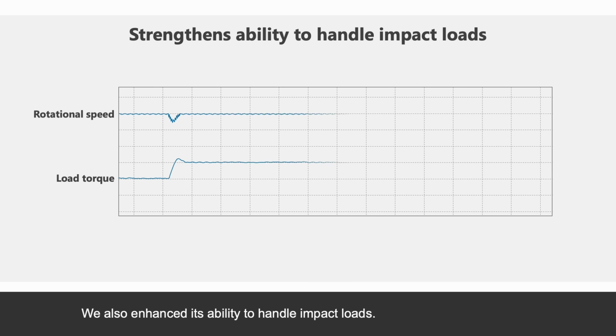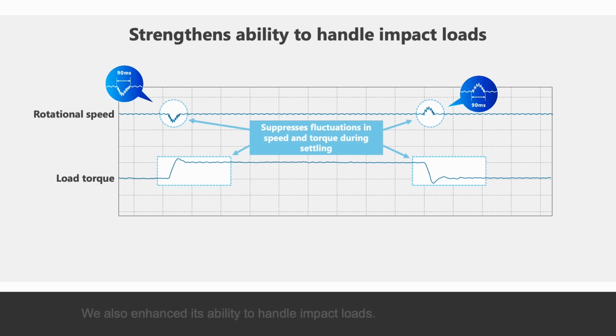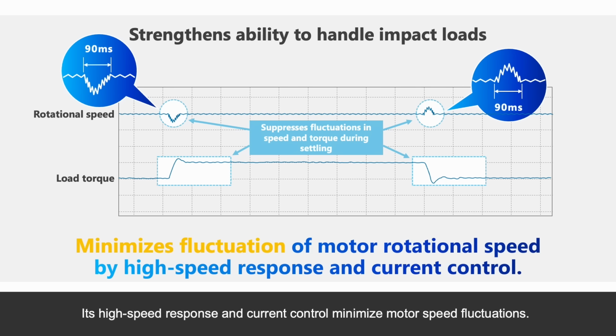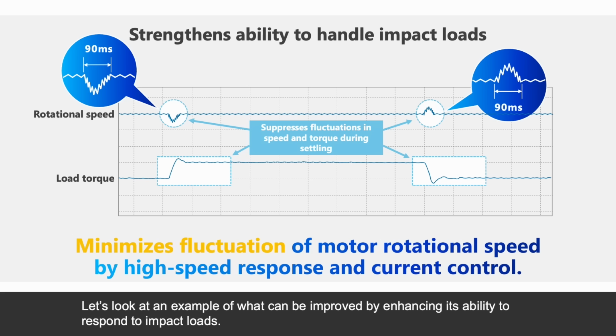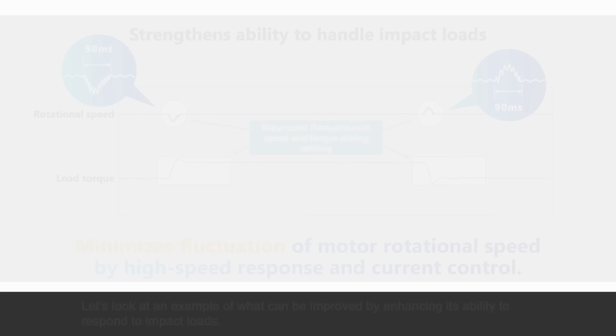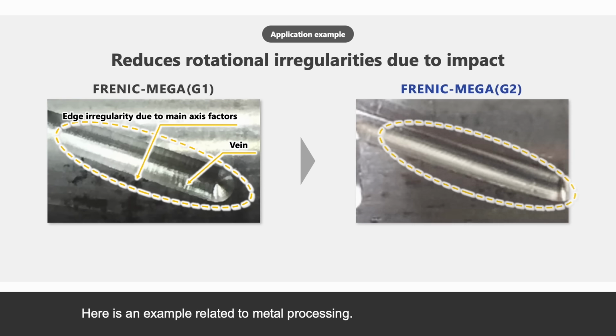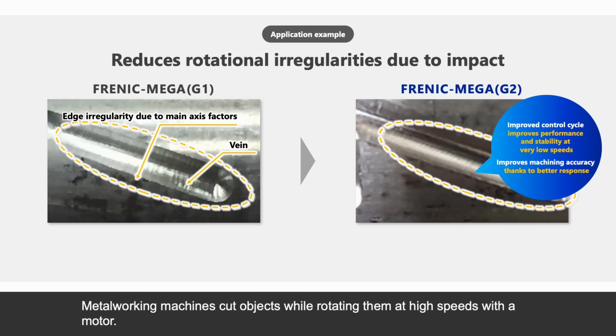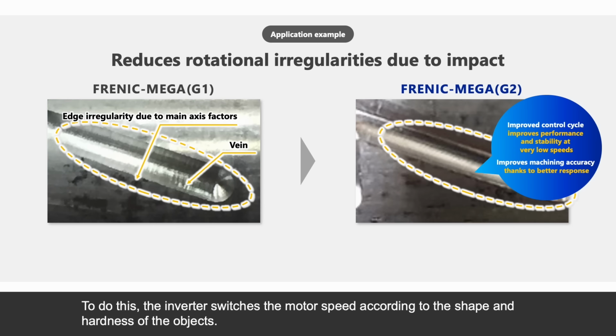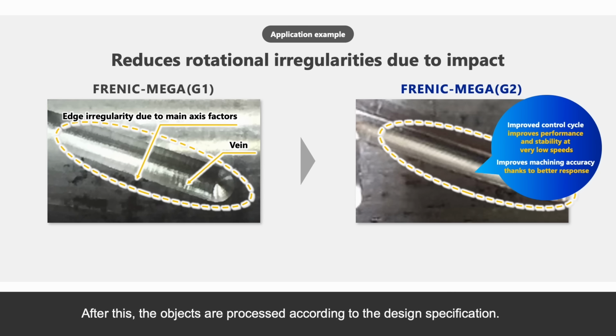We also enhanced its ability to handle impact loads. Its high-speed response and current control minimize motor speed fluctuations. Let's look at an example of what can be improved by enhancing its ability to respond to impact loads. Here is an example related to metal processing. Metalworking machines cut objects while rotating them at high speeds with a motor. To do this, the inverter switches the motor speed according to the shape and hardness of the objects. After this, the objects are processed according to the design specification.